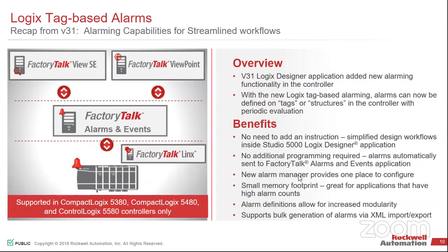And if you remember the ALMDs, ALMAs, we would give you a hard limit and say, do not exceed more than this on a controller because issues can happen. Most of the time that was down at the 250 to 500 level. These newer alarms, even though they're not as heavy as an ALMA, ALMD when it comes to memory, they're a fraction of the memory usage required on those. We're probably closer to the 1,000, 2,000 range of how many alarms we would want in a controller.